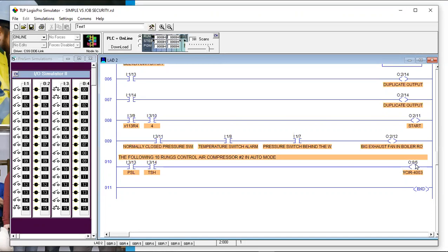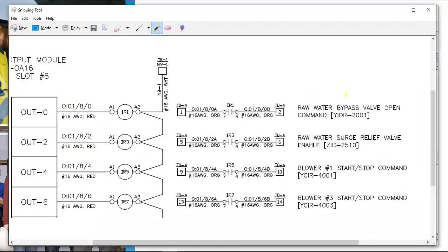Here we have output eight-six with a cryptic-looking label. Let's look at where the schematics came from. Here is the output module in slot eight, and down here is output six, turning on something called IR7 — a coil of a relay or starter coil. Going all the way over in the schematic, what are we actually turning on? Blower number three. We didn't have room in the logic to write all this, so we put it on the schematic. Now it matches both the logic and the schematics.